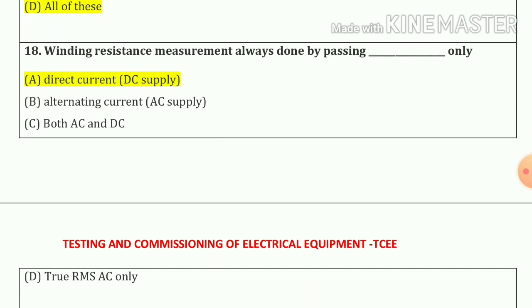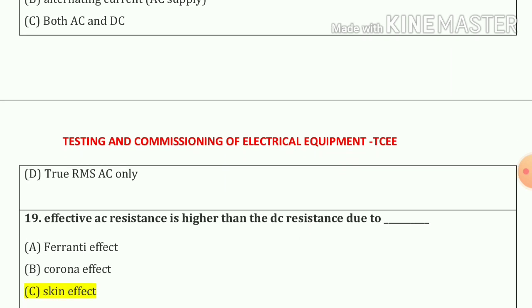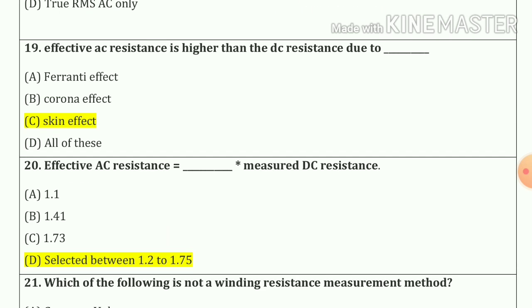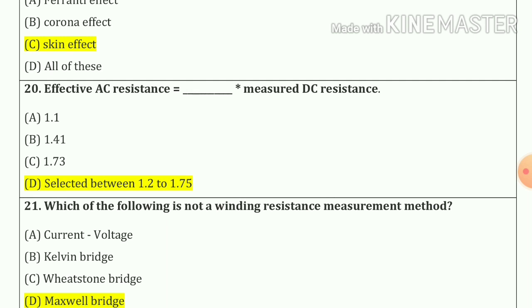Now question number 18. Winding resistance measurement always done by passing DC supply only. Question number 19. Effective AC resistance is higher than DC resistance due to skin effect. Now question number 20. Effective AC resistance is equal to a multiplication of 1.2 to 1.75 times the measured DC resistance.